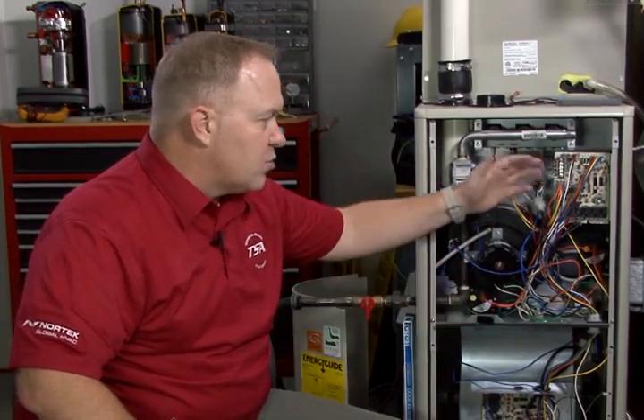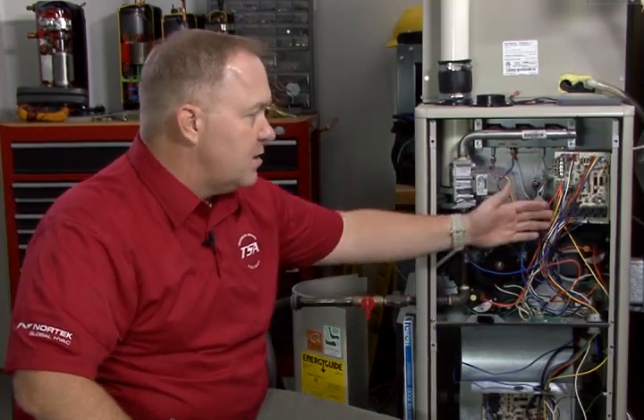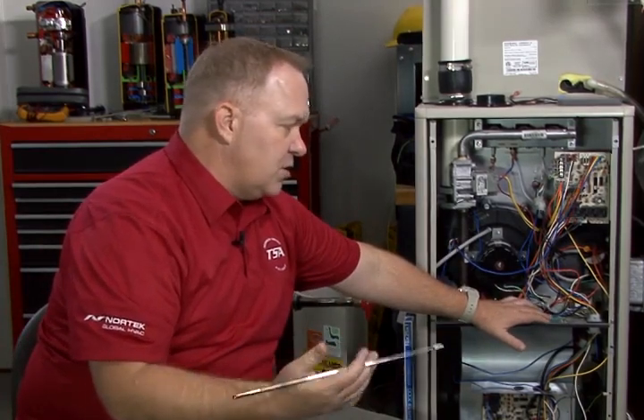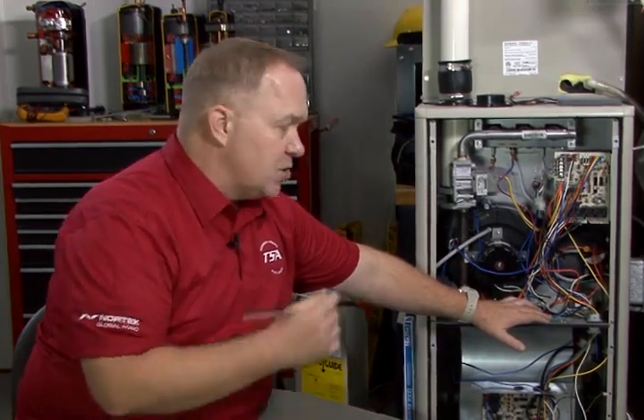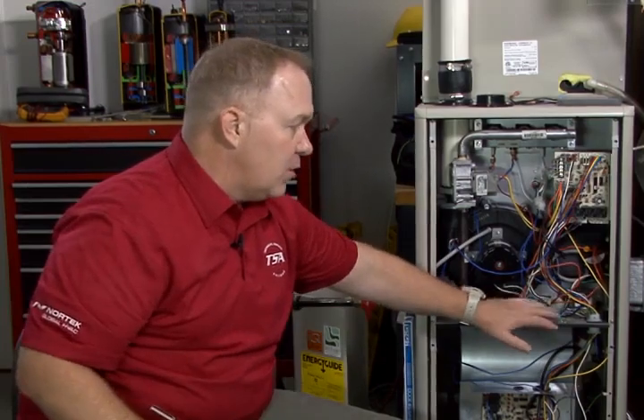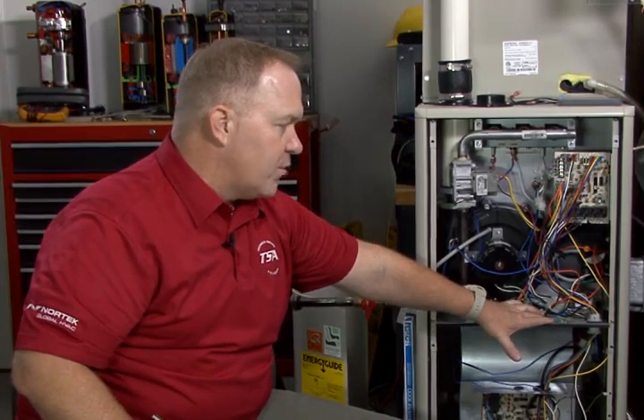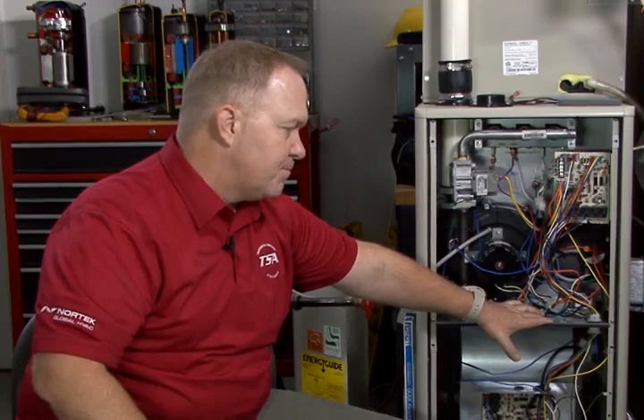Without having proper ground, you can be in a floating ground condition, and the board may struggle to actually operate and perform all of the functions that it properly should. If you do not have a ground, like let's say it's an older home, you discover that you only have a hot and a neutral, you're going to want to add an external ground and wire that up for the furnace. Otherwise, it could struggle right off the bat with being able to prove flame.